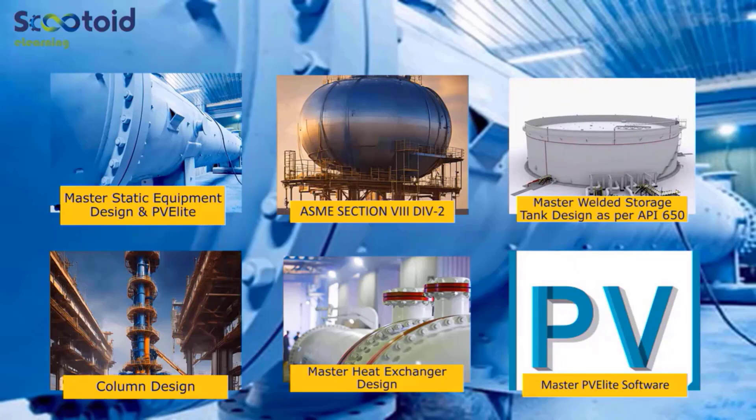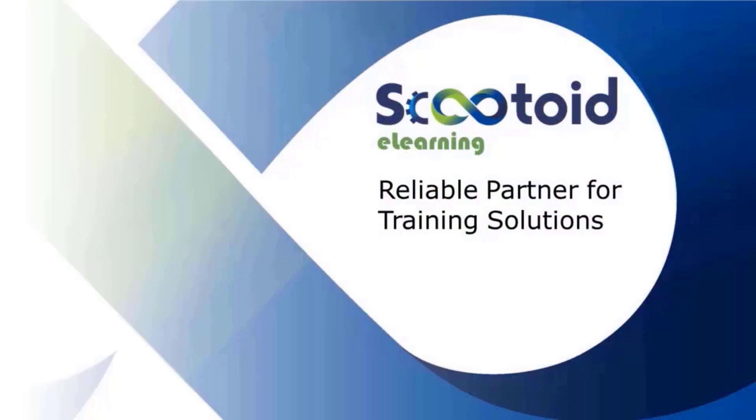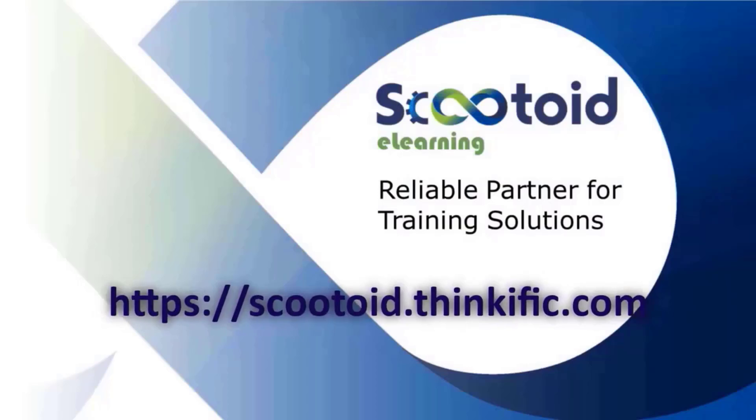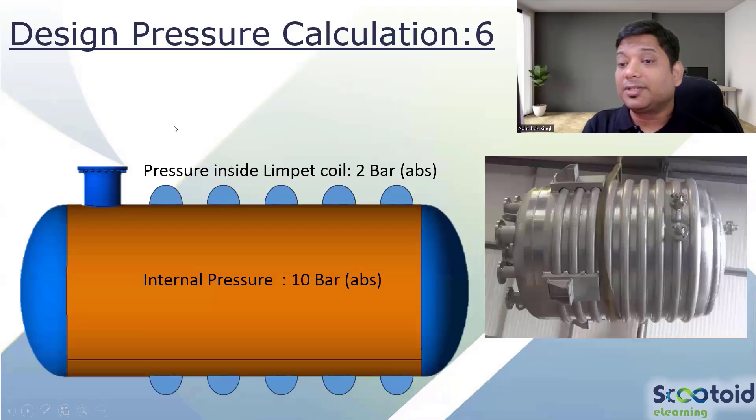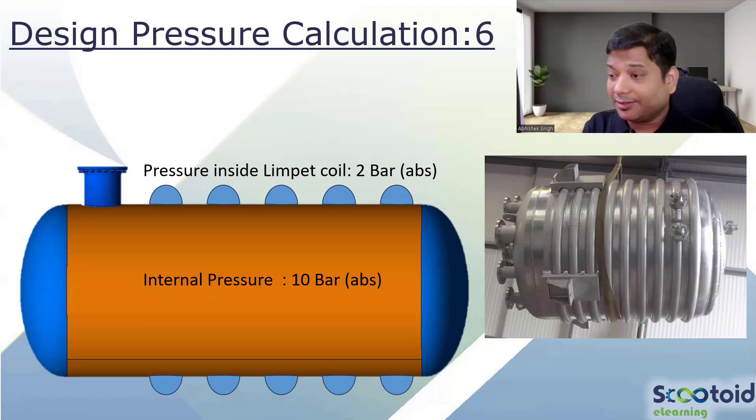This is calculation 6, very interesting. Most of the time you will get that limpet coil scenario. We have a 10 bar absolute pressure in the vessel, limpet coil with 2 bar absolute, and atmospheric as usual 1 bar.